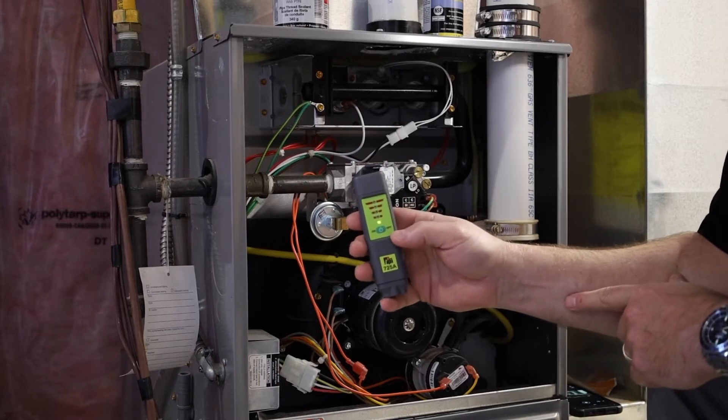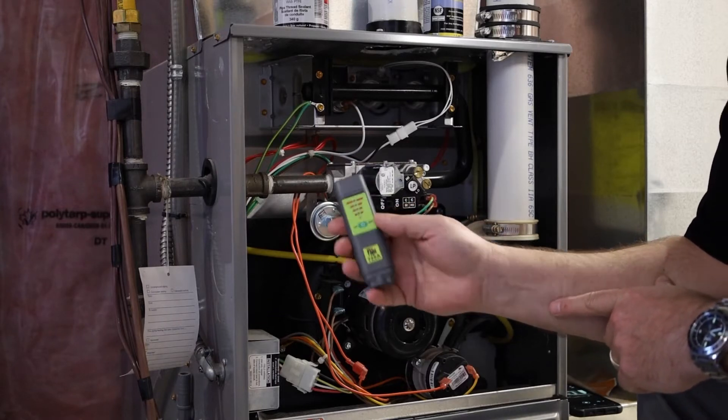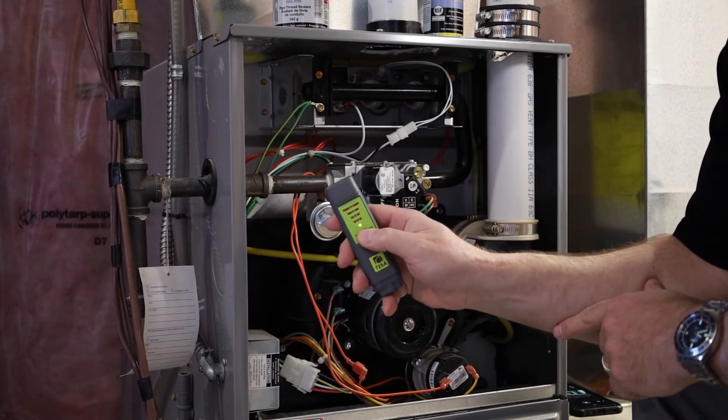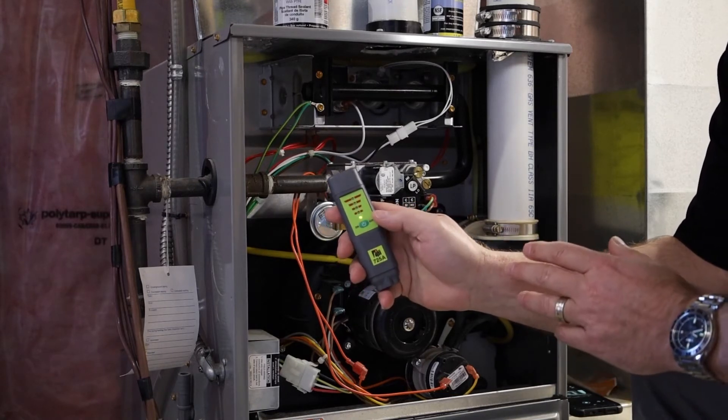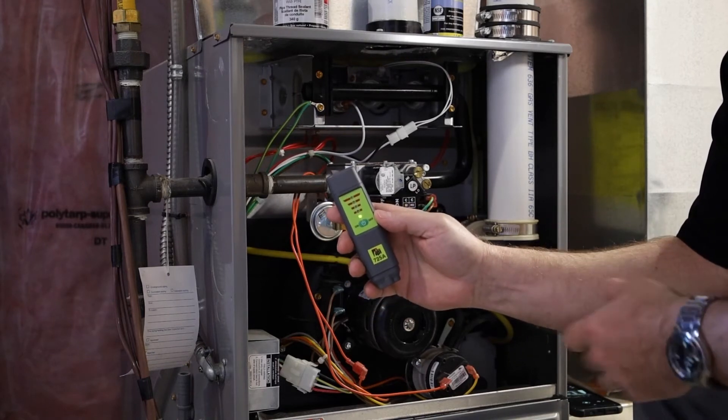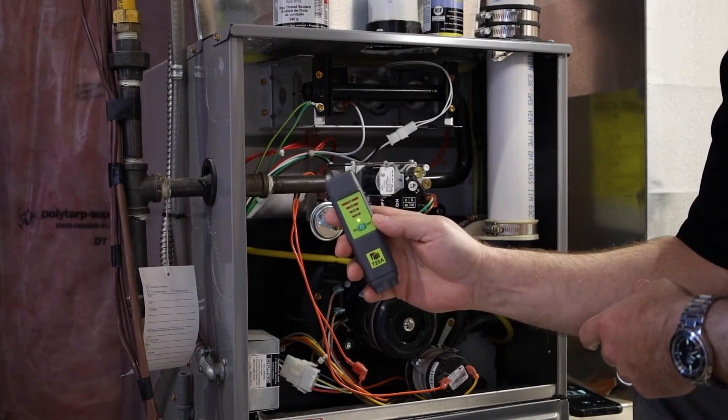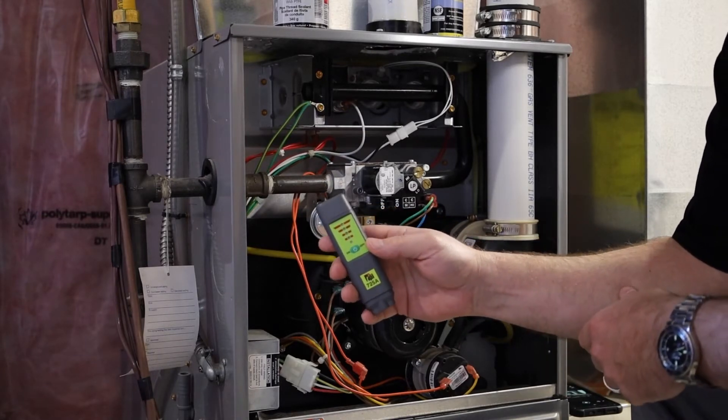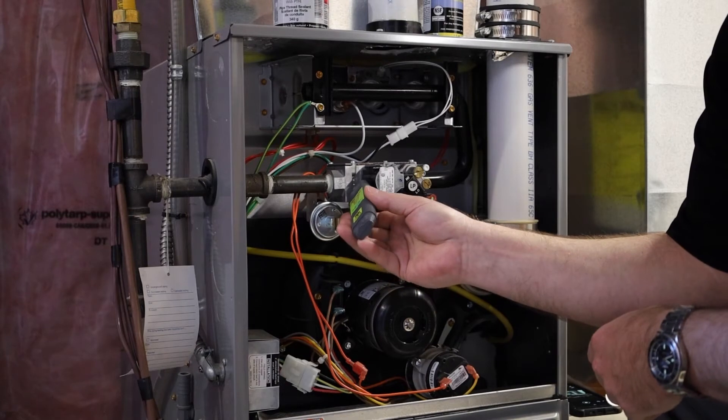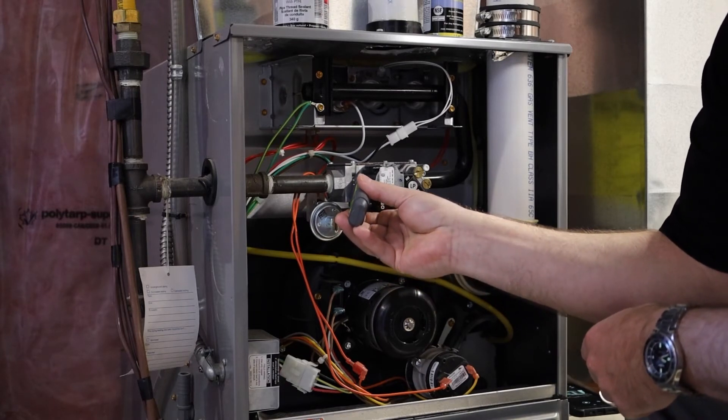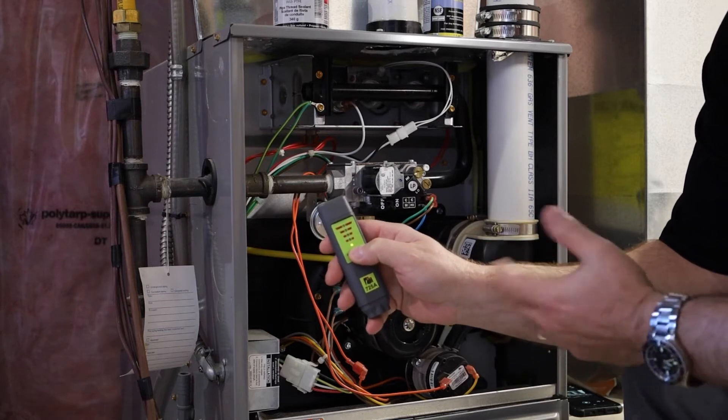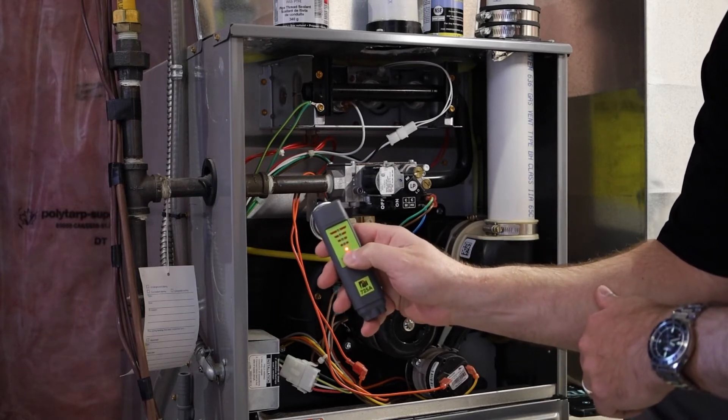Now with this leak detector when you detect a leak you can press a button and zero it out. So now it is only going to detect higher combustible gases, a higher sample of parts per million. So again go over to my suspected leak and there it goes. Obviously the higher it is, that's where the source of the leak is going to be.